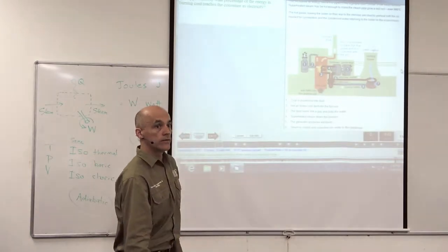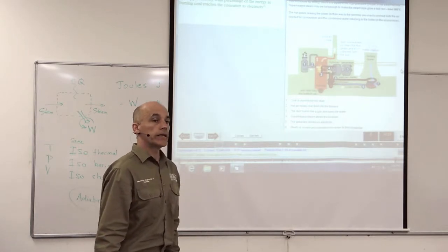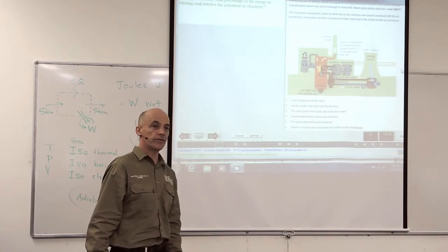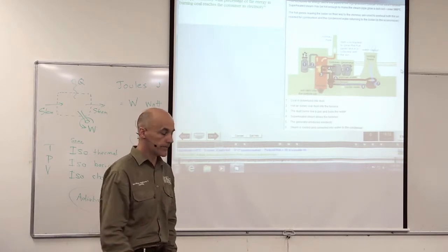But the biggest loss of all is that the steam has to come out of the turbine hot. That's why there's a big loss. So it's coming in really hot. It's red hot pipes of steam coming into the turbine. And then going out of the turbine, it's not allowed to get too cold because then it starts to turn back into water. And if it does that, it'll hit the blades and erode them very quickly. So they have to still be quite hot when it comes out. That's why we have a loss.